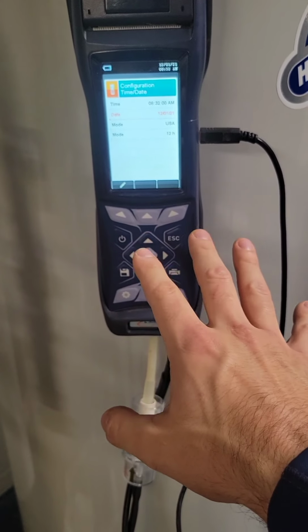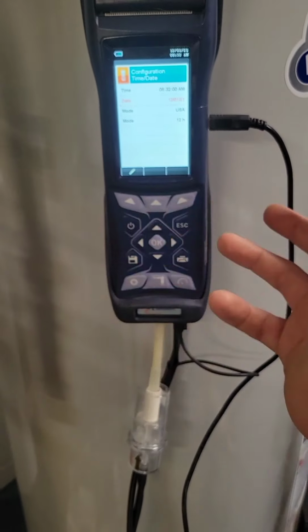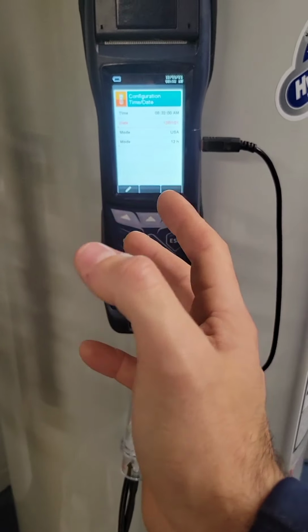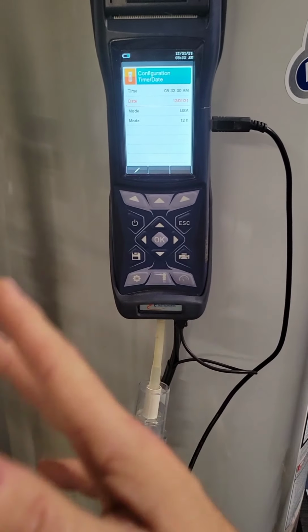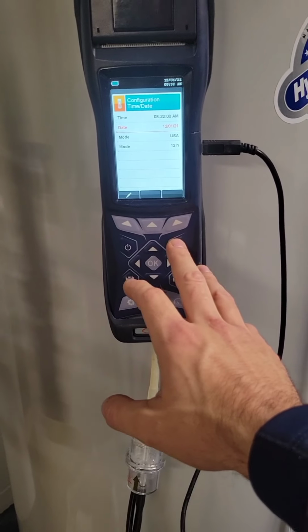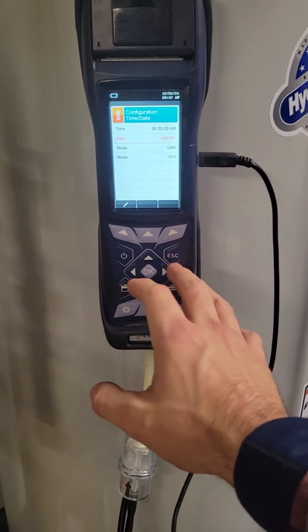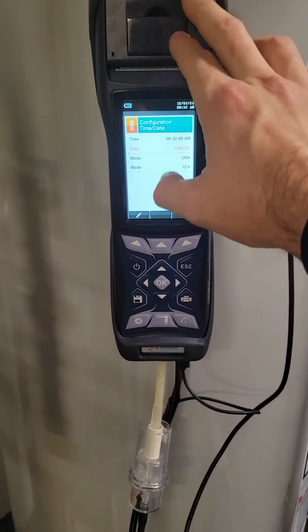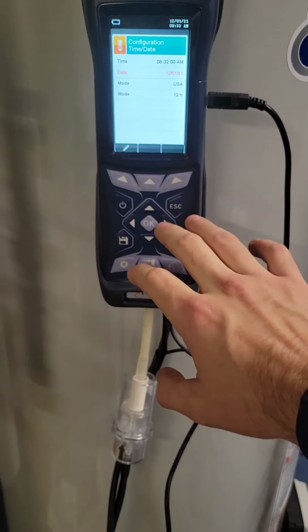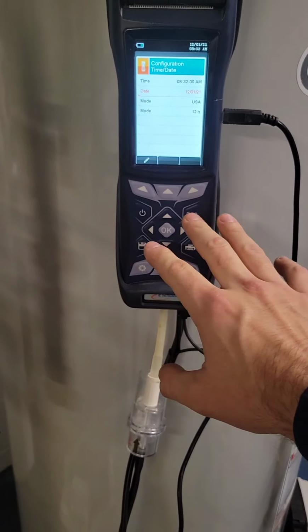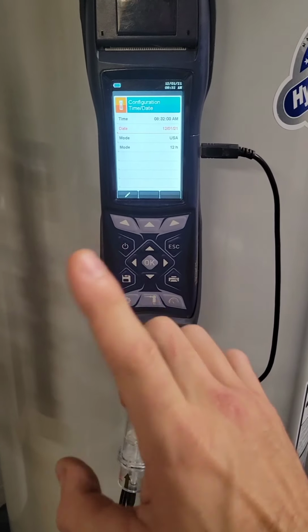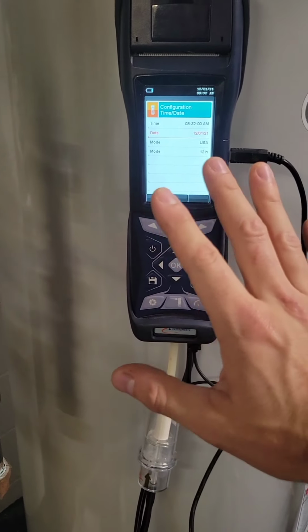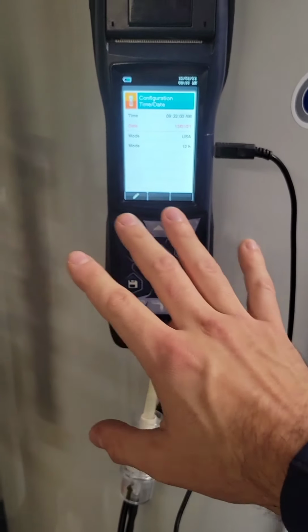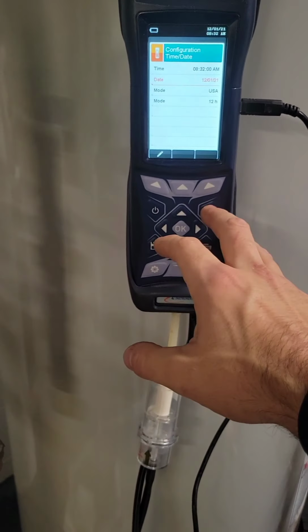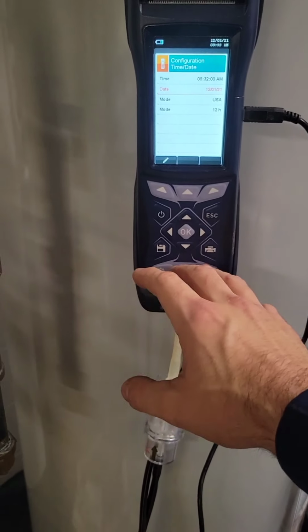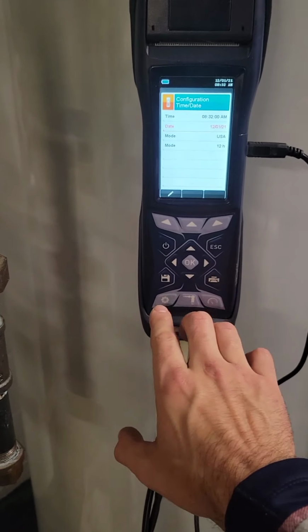You always want to make sure this is correct, because God forbid, let's say something happens and this needs to be used for purposes like legal purposes or anything like that. You want to make sure this is as accurate as possible. You also want to calibrate these every year. No matter what combustion analyzer you have, you always want to calibrate it every year. If it's not calibrated, and something happens within that year, even though you have a history of what you did, it's invalid, because it wasn't calibrated. So definitely get it calibrated every year if you get a chance.